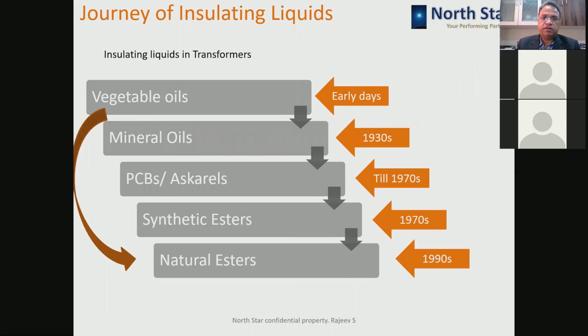So if you look at the journey of insulating liquids, when transformers were invented and came into commercial production, the liquid insulation was vegetable oils, normal edible vegetable oils put inside the transformer as an insulating liquid. Then mineral oil came into existence in 1930. Then till the 1970s, PCBs and Askarels were used in transformers. Due to carcinogenic properties and other harmful effects, PCBs were banned, and in 1970, synthetic esters also came into the picture. So along with mineral oil, synthetic esters were also available as an insulating liquid in transformers.